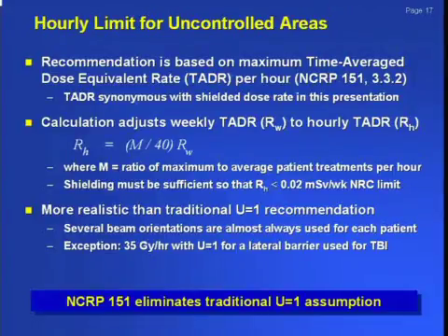that you don't exceed more than 0.02 millisieverts per week, which was originally your NRC limit. That's what we tend to refer to it as, the NRC limit. But obviously that is the same limit that is adopted by all the states in their suggested state regulations. So you do have to verify that your time average dose rate, or your exposure rate, is not going to exceed 0.02 millisieverts per week at any point for the public.